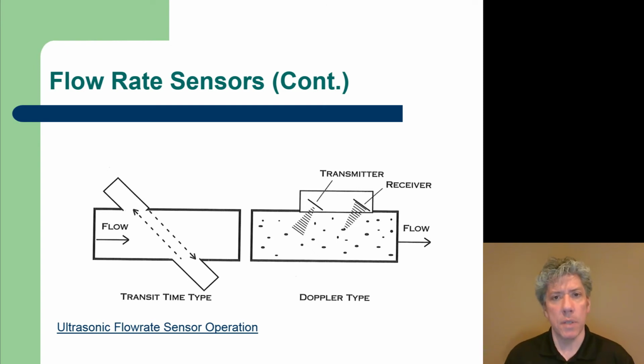Other types of sensing technologies use sound. The first type here on the left is a transit time type, where there are transmitters and receivers at both ends of the pipe. So at the lower end there's a transmitter, and at the upper end there's also a transmitter. Both send a sound pulse and measure the amount of time it takes for that sound pulse to go across. When there is no flow, of course the amount of time required is the same, but when there is flow, one transmits faster than the other. And again, I'll let you watch the video to see more detail of that.